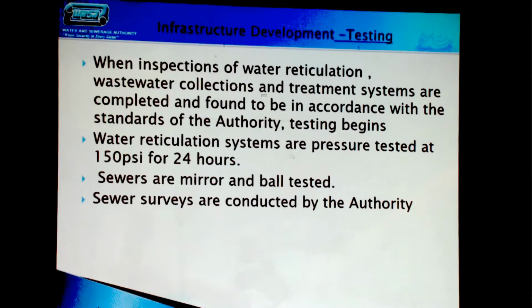The wastewater treatment plants and lift stations are run with a hydraulic loading. We run the blowers and we test it. But anybody in the wastewater industry will tell you that a treatment plant doesn't begin operation immediately when you start it up. There's a seeding period and a commissioning time. So you may be required to provide, not to us, but to the EMA after the fact, in accordance with your CEC, that the treatment plant meets the required standards.